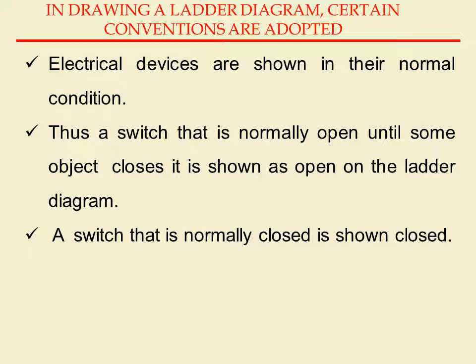In a ladder diagram, the electrical devices are shown in their normal condition. Thus a switch that is normally open until some object closes it is shown as open in the ladder diagram. A switch that is normally closed is shown as closed in the ladder diagram. And after any action happens, it is open.